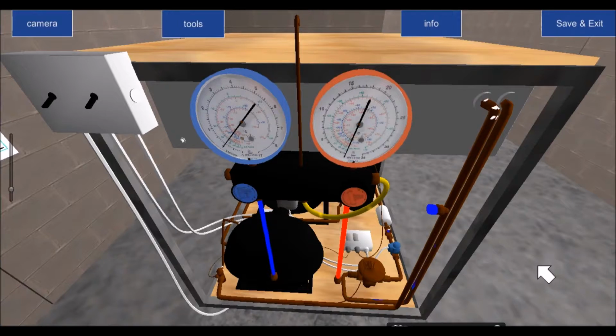You might have heard established fridge men talking about the process of topping up. It's illegal. Don't do it. Regardless of what a shopkeeper says, a shopkeeper that's in the business a very long time might have been used to that practice. They might insist that you do it. Don't do it, because you will be prosecuted. They will be prosecuted, and you will be prosecuted. So it is very important that you understand that under the F-gas regulation, a contractor or an operator that knowingly adds refrigerant to a system that they know has a leak, or even suspect has a leak, and haven't signed off on it, is against the regulation. That's illegal, and you can be prosecuted for it. So it's important that we're aware of that.